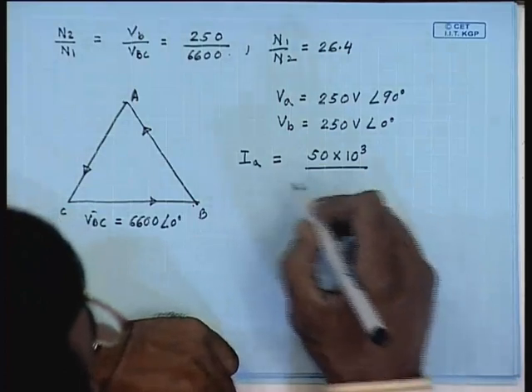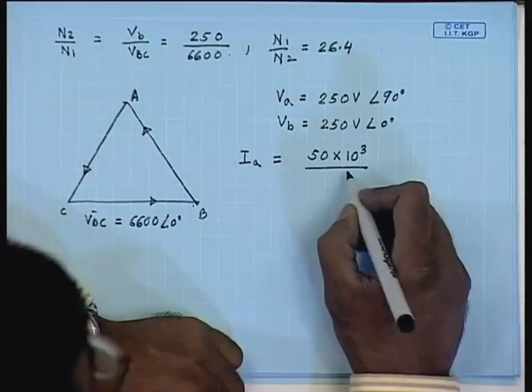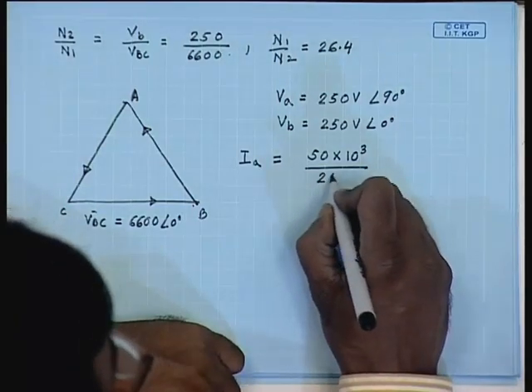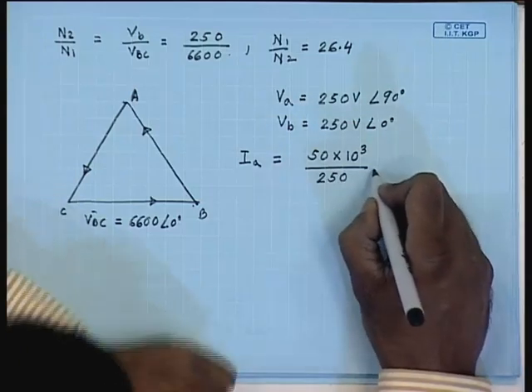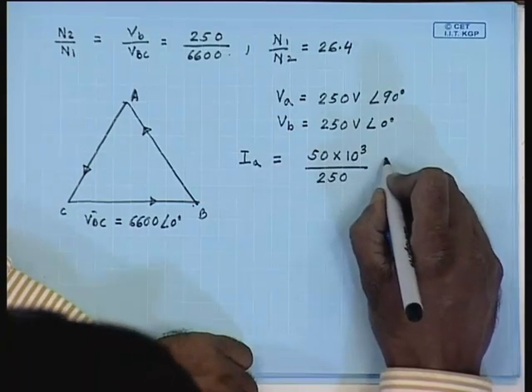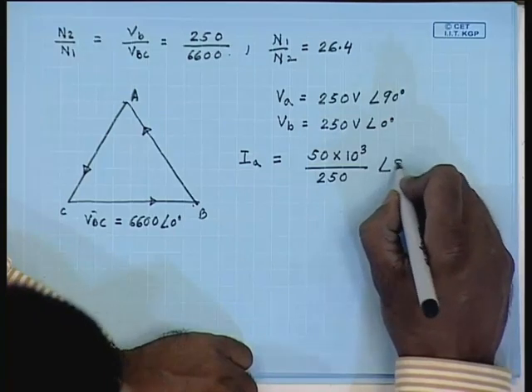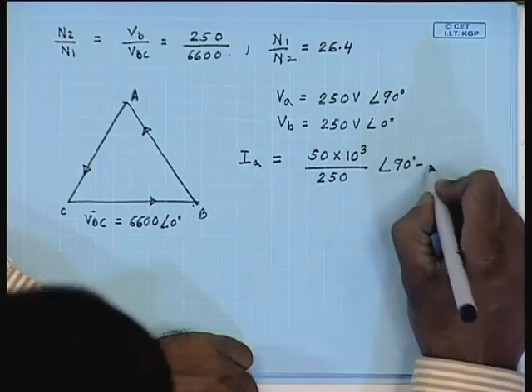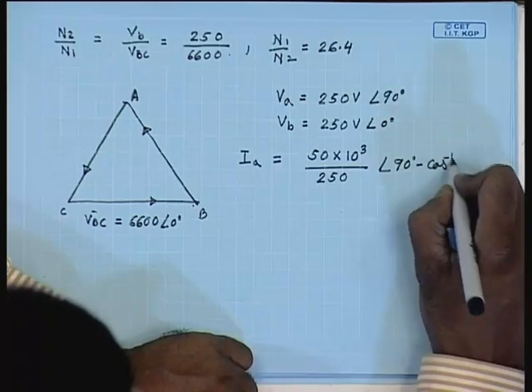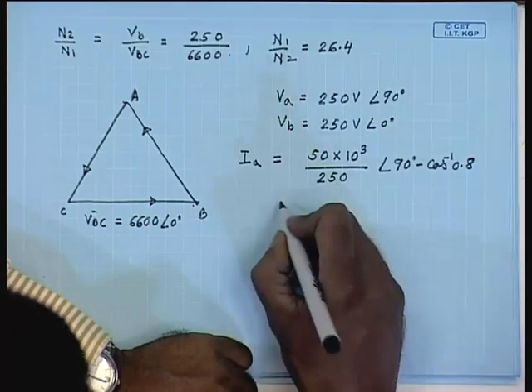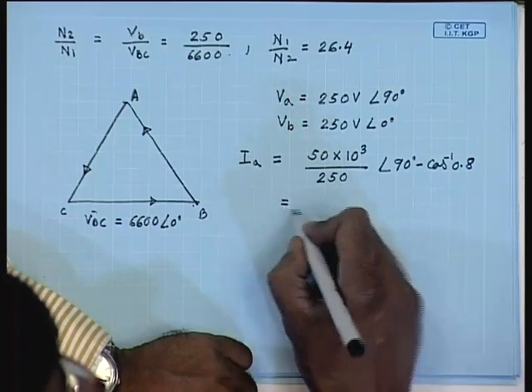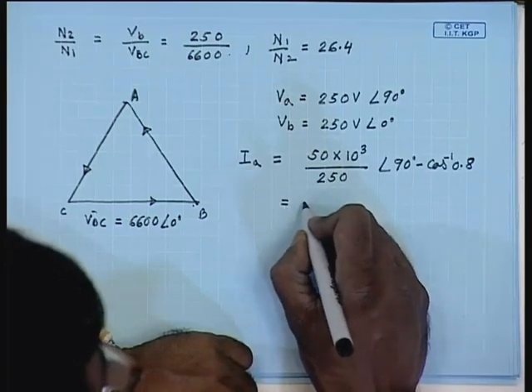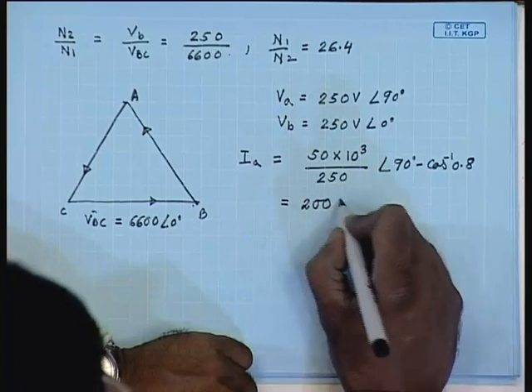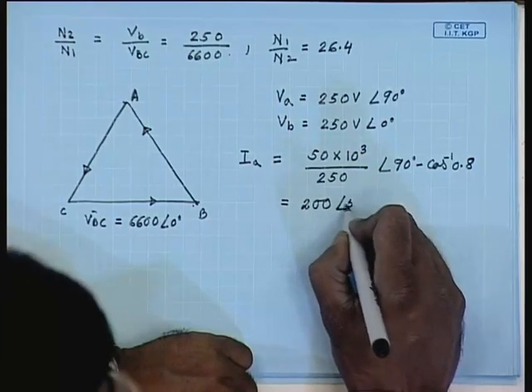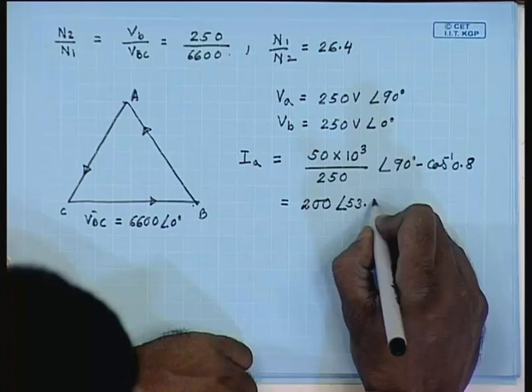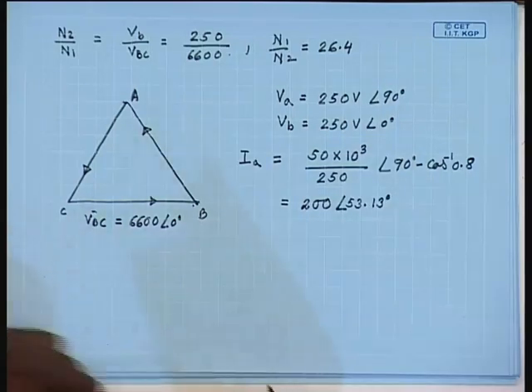So the load current IA is 50 kVA divided by 250, at an angle of 90 minus cos inverse 0.8, or IA equal to 200 amperes at an angle of 53.13 degrees.